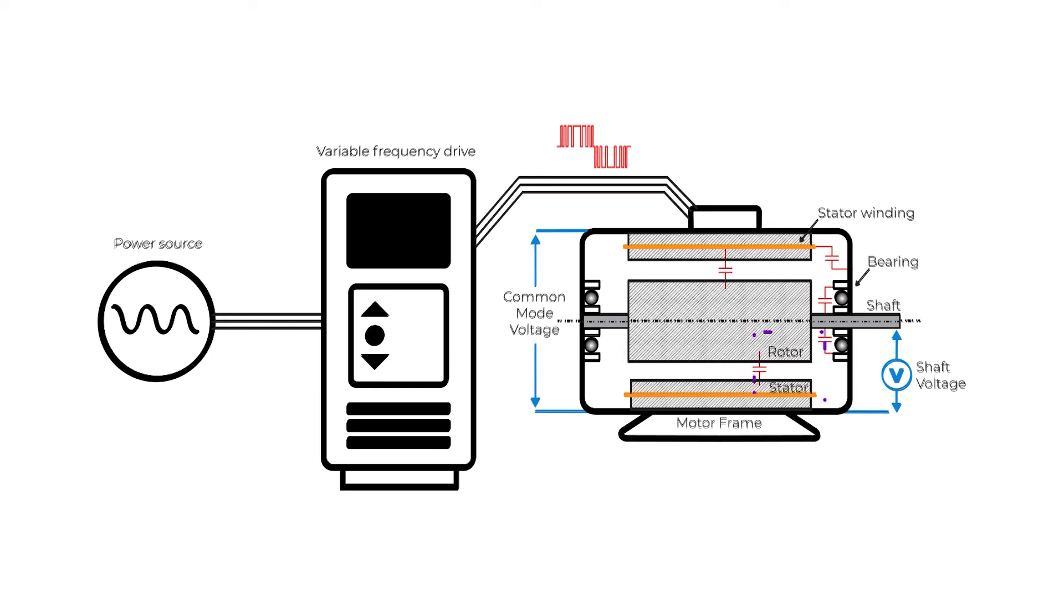DVDT of the common mode voltage in the stator windings generates pulse currents flowing to the rotor. Part of this current flows between the inner race and the outer race of the bearings, causing heat in the lubricant.